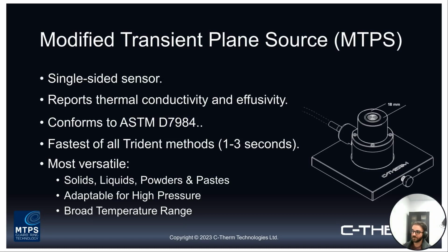It reports out thermal conductivity and effusivity, conforms to ASTM D7984, which is specified to the effusivity measurement there. It is the fastest of all the Trident methods.